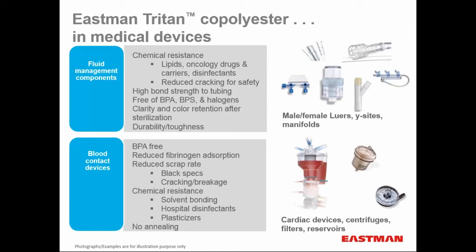Finally, let me share a few examples of applications where Tritan is currently being used. In fluid management components, there is wide acceptance of male and female Luers, Y-sites, and manifolds. This is largely due to chemical resistance — good resistance to lipids, oncology drugs and their carriers, and disinfectants — and overall reduced cracking rates for a heightened sense of safety. Very high bond strength of tubing. No chemicals of concern: BPA-free, BPS-free, halogen-free, no plasticizers, no phthalates. Excellent clarity and color retention even after sterilization through ethylene oxide, E-beam, or gamma sterilization. Outstanding durability and toughness. In blood contact devices — cardiac devices, centrifuges, filters, reservoirs — Tritan is BPA/BPS-free with no halogens or materials of concern. We're also putting together a data package showing Tritan has reduced fibrinogen adsorption on the surface, which is important because fibrinogen adsorption is the first step to clotting in blood oxygenators.